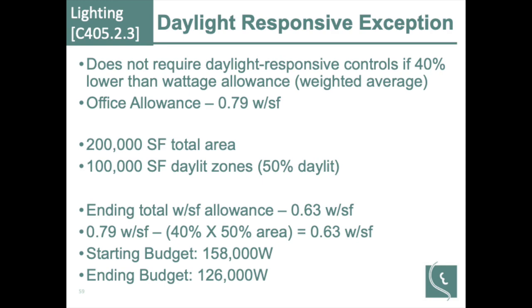When do you have to put in the daylight harvesting? If you have over 150 watts in the daylit zone, whether that's the top lit zone or the side lit zone. Is that in every building, or is it just offices, or what? This is in the code. I believe it's all buildings with some certain exceptions. They do have certain exceptions in the code, as far as I know, for large manufacturing. There's a couple of assembly areas, and then there's a few other areas in the code that exclude them. But generally speaking, if you're over 150 watts in the daylit zone in a commercial building, daylight harvesting is required.